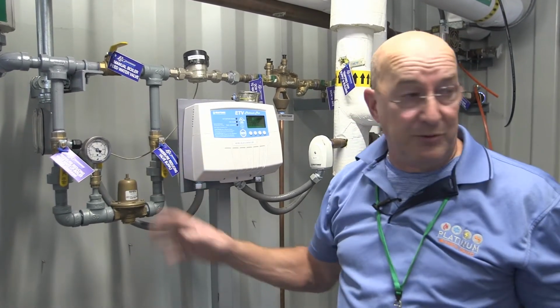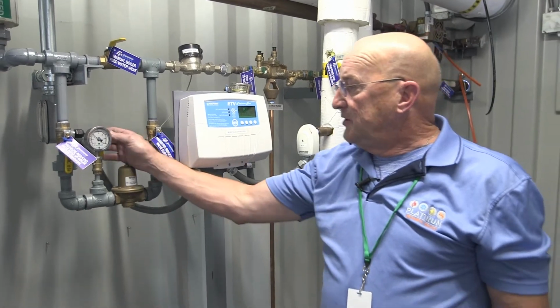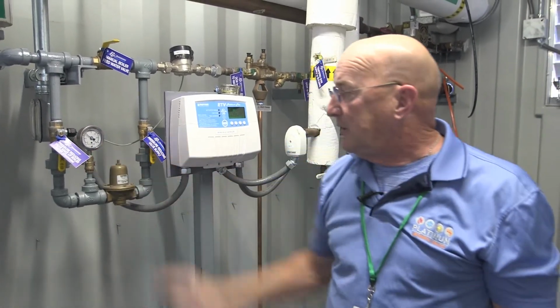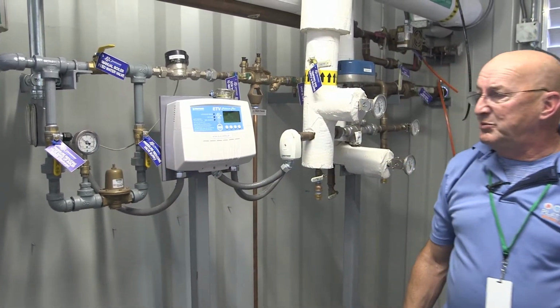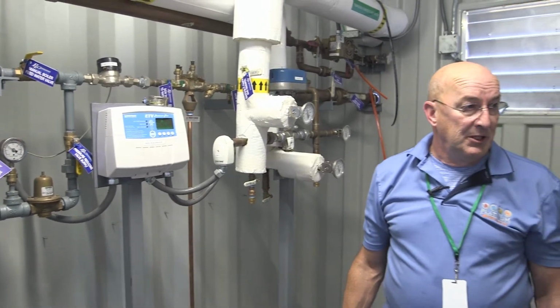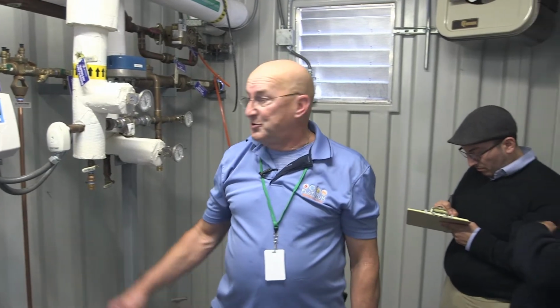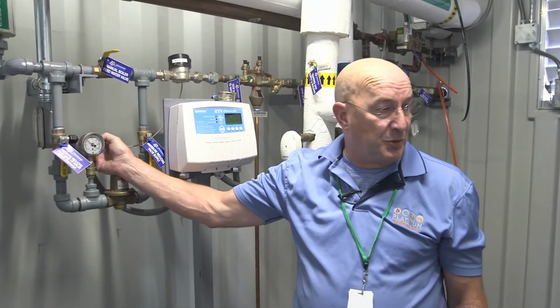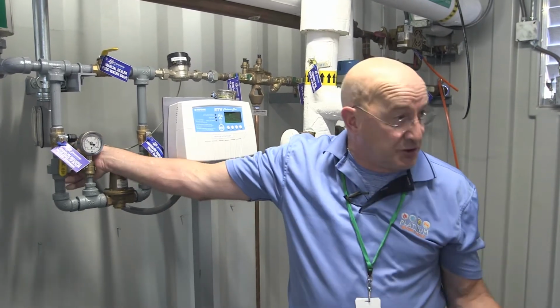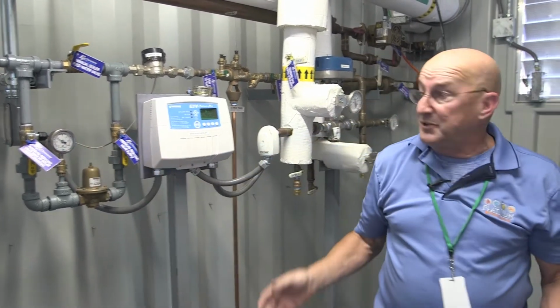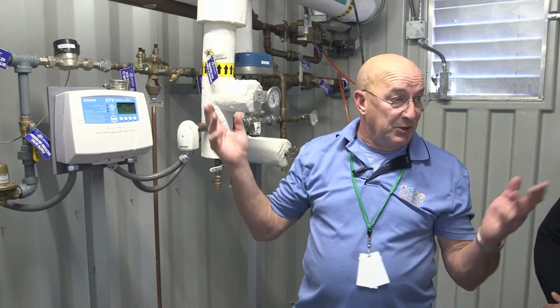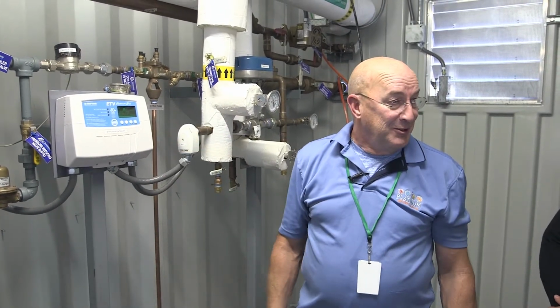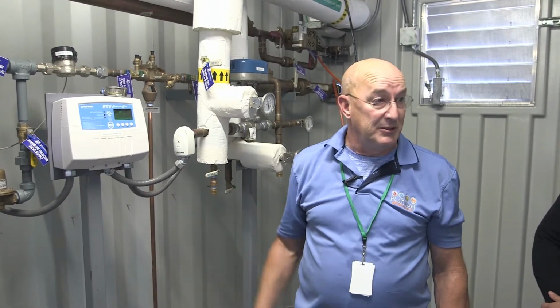Again, it's valved off for any reason. This valve here is on a gauge. Any pressure gauge that has a valve, the valve should be in the off position. It should not be on. It's strictly if you want to walk up here and ask how much pressure there is: you open it up, it reads the pressure, and then you shut it off. Otherwise, valves fail, they blow up, and you get floods in here. You don't need that aggravation. So make sure any pressure valve stays shut.